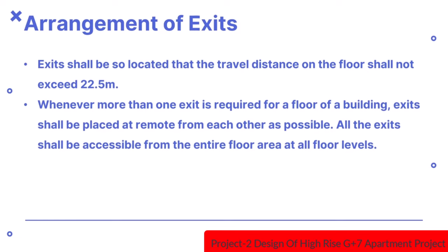Exits shall be so located that the travel distance on the floor shall not exceed 22.5m. Whenever more than one exit is required for a floor of a building, exits shall be placed as remote from each other as possible. All the exits shall be accessible from the entire floor area at all floor levels.